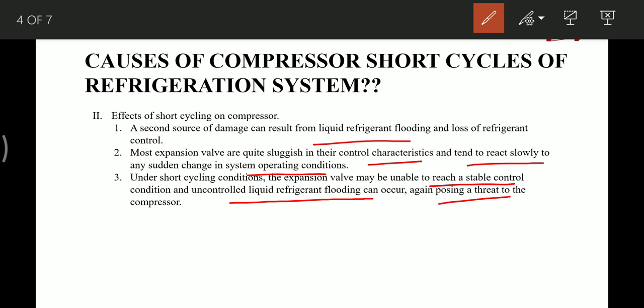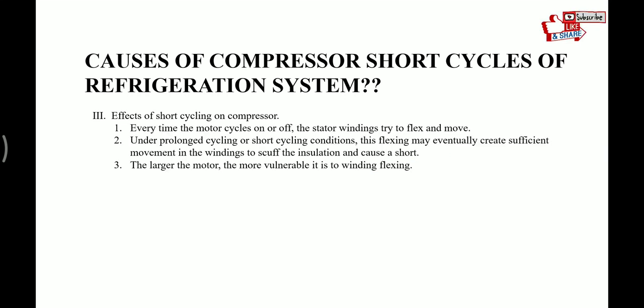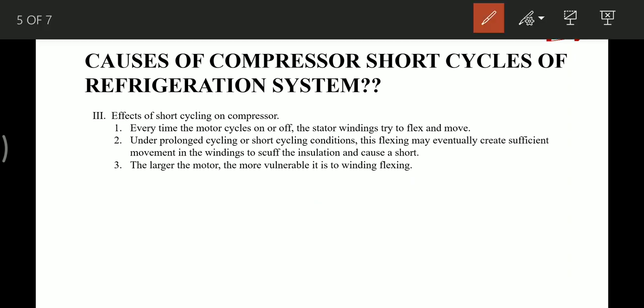The next fault that short cycling causes is that every time the motor cycles on and off, the stator winding tries to flex and move. Under prolonged or short cycling conditions, this flexing may eventually create sufficient movement in the winding to scuff the insulation and cause short circuit.